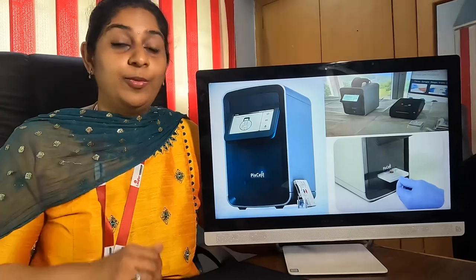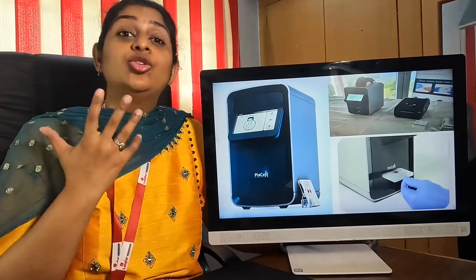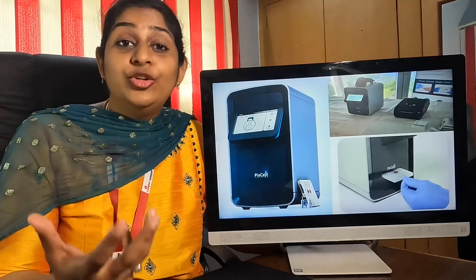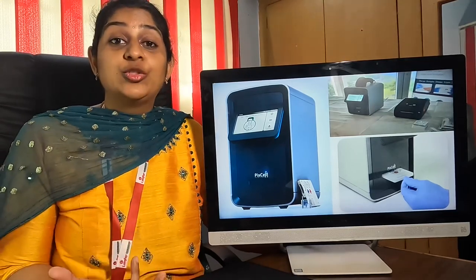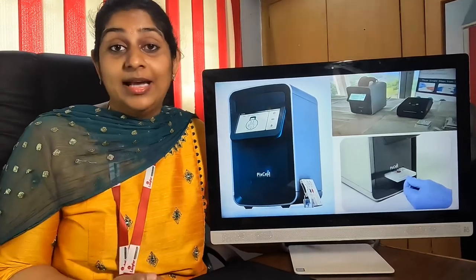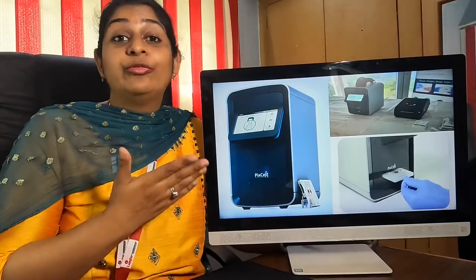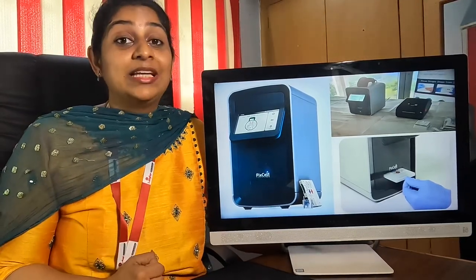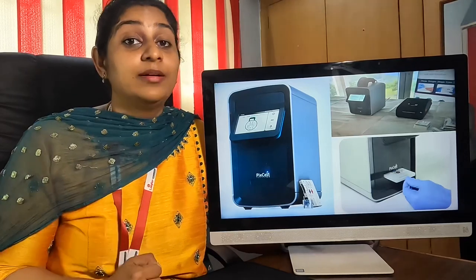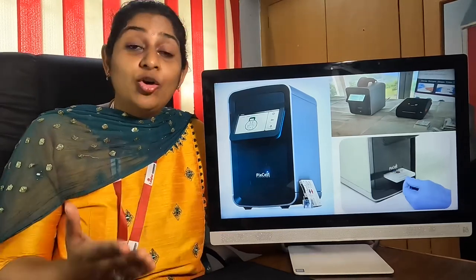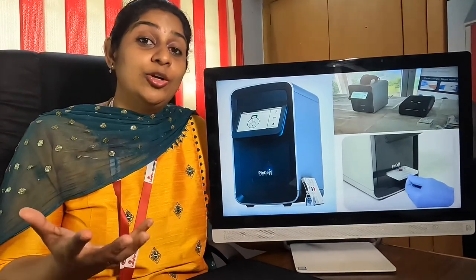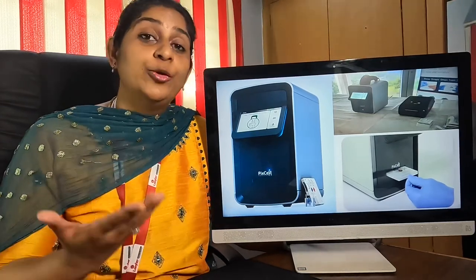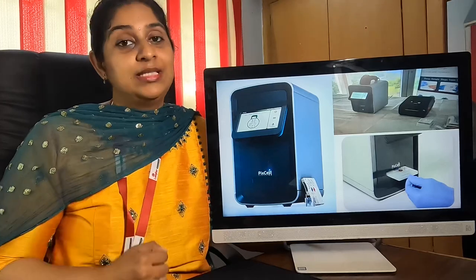The fifth point is the throughput of your machine. According to the workload of your center, you have to choose wisely. A machine can give 40 samples per hour, and some machines can give 60 samples per hour as a throughput. According to the sample load you are going to get at your center, you need to choose how much throughput you need.